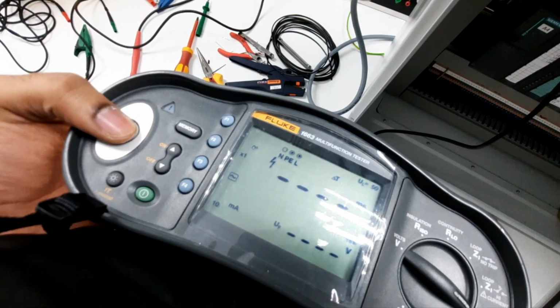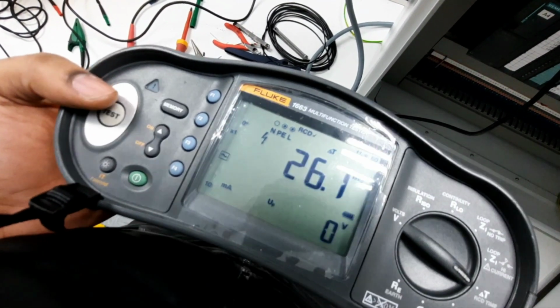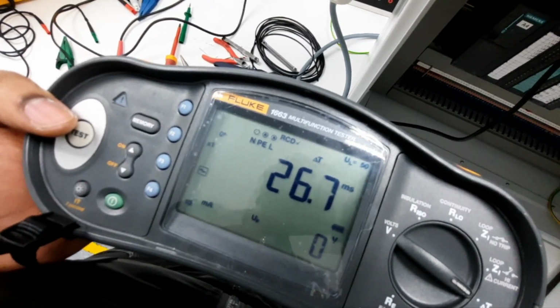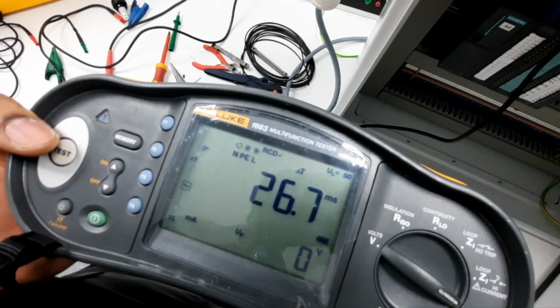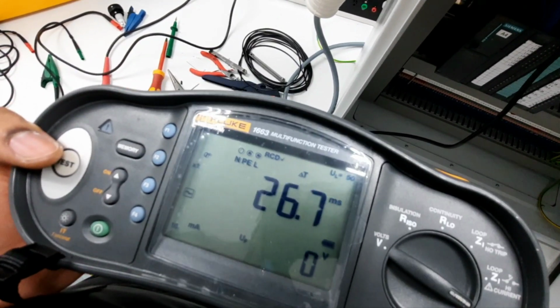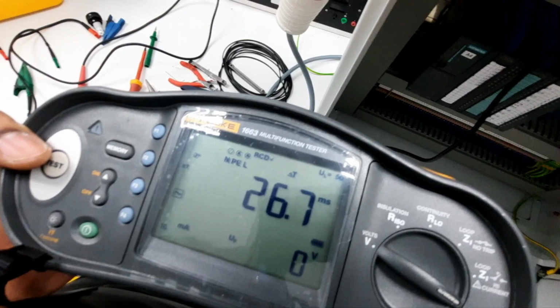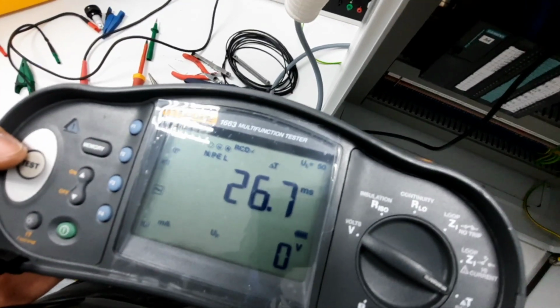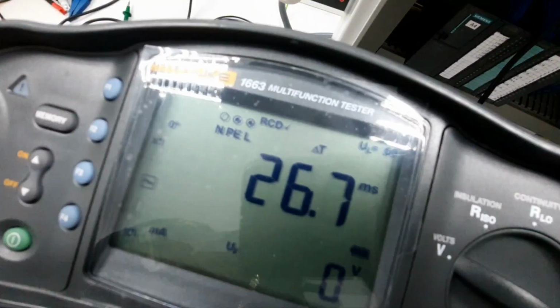Okay, so now you can test. So this is the trip time, 26.7 milliseconds. So the condition is actually less than 40 milliseconds, then okay. So this one is very fast. And down there is your contact voltage, so it's either 0 or 1. That is the contact voltage, 0 or 1. This one is the trip time, which is 26.7 milliseconds.